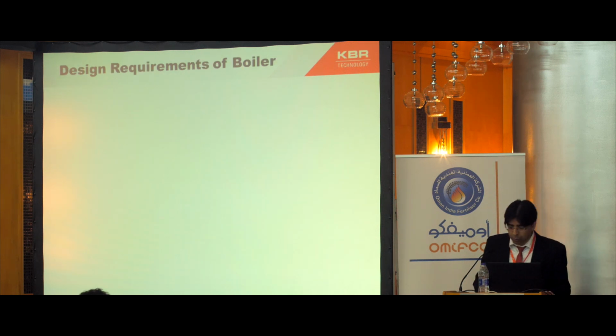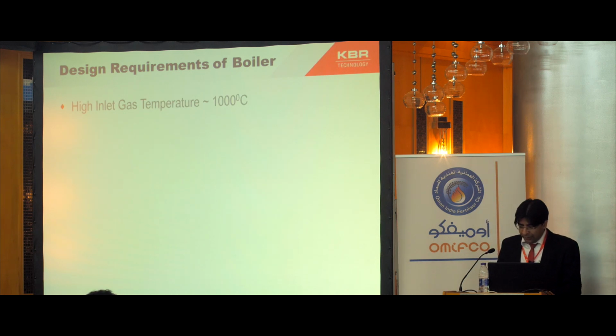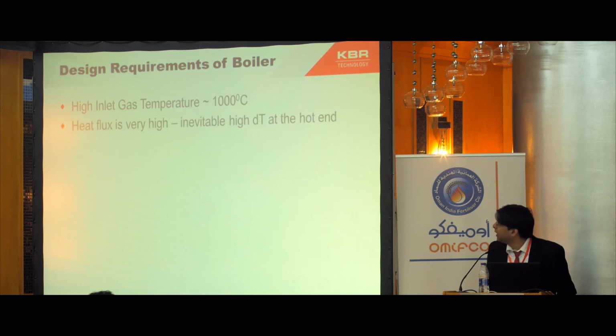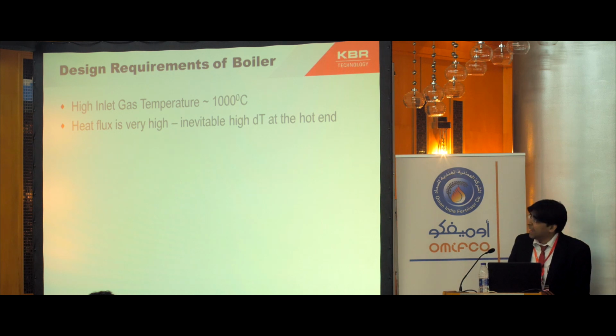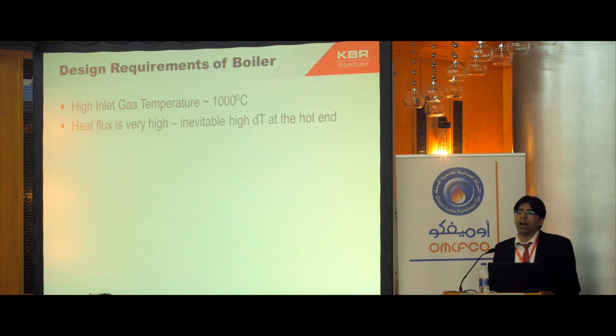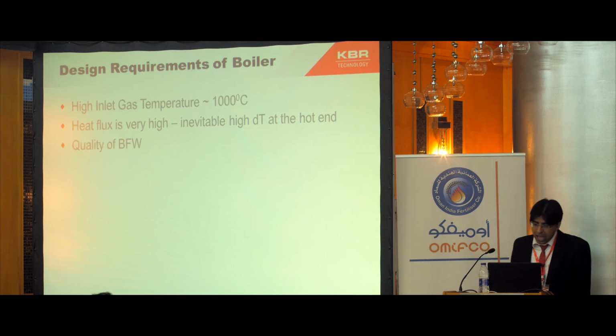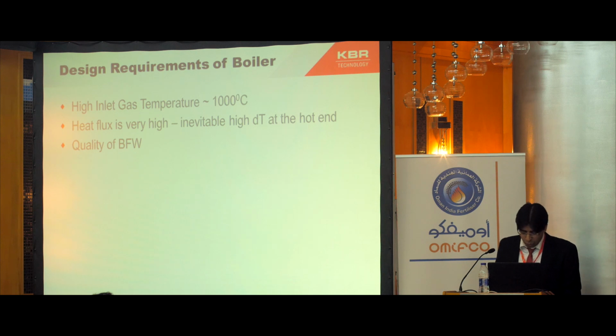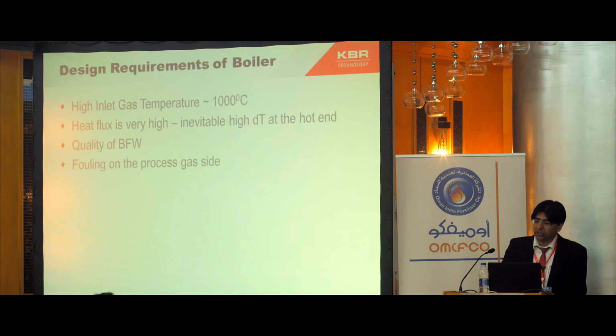Reviewing the design requirements of this boiler, we see that the gas temperature entering the boiler is 1000 degrees C, which is extremely high, and it also leads to very high heat flux with an inevitable high DT at the hot end. ASME guidelines state that this heat flux will require above normal boiler feed water treatment practices. This service is very sensitive to boiler feed water chemistry. So if it becomes abnormal, it will lead to corrosive failures of this waste heat boiler. Due to this high inlet gas temperature and high heat flux, the boiler feed water fouling will have a dramatic impact. If the steam drum goes dry, the boiler will immediately fail.